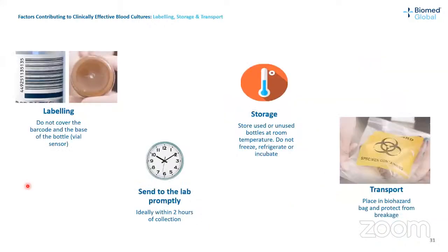When it comes to labeling of your bottles, there are 2 areas which should never be covered with the patient sticker. The first one is the barcode, because the barcode needs to be scanned by the machine. The second place is the base of the bottle, where you would find your vial sensor. These 2 areas should never be covered with the patient sticker, or else your sample cannot be processed.